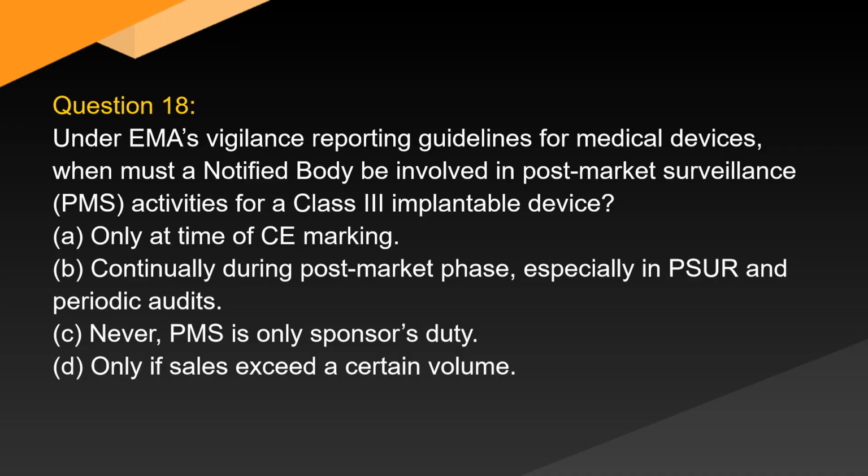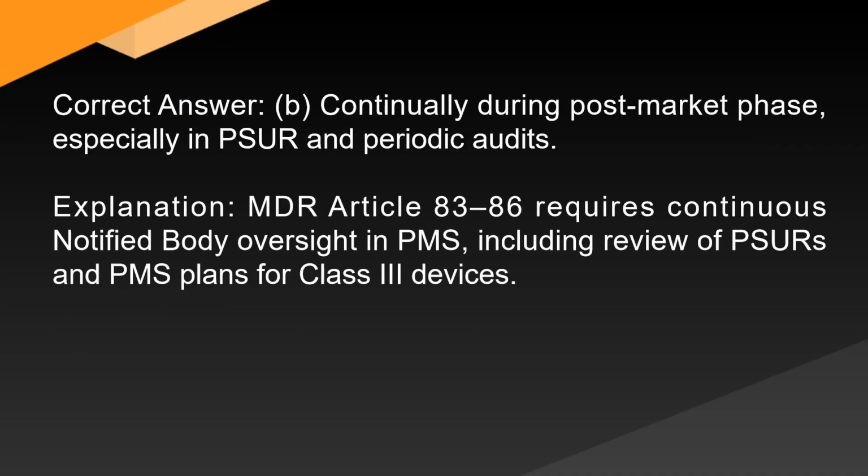A. Only at time of CE marking. B. Continually during post-market phase, especially in PSUR and periodic audits. C. Never. PMS is only sponsor's duty. D. Only if sales exceed a certain volume. Correct answer. B. Continually during post-market phase, especially in PSUR and periodic audits. Explanation. MDR Article 86 requires continuous notified body oversight in PMS, including review of PSURs and PMS plans for Class III devices.